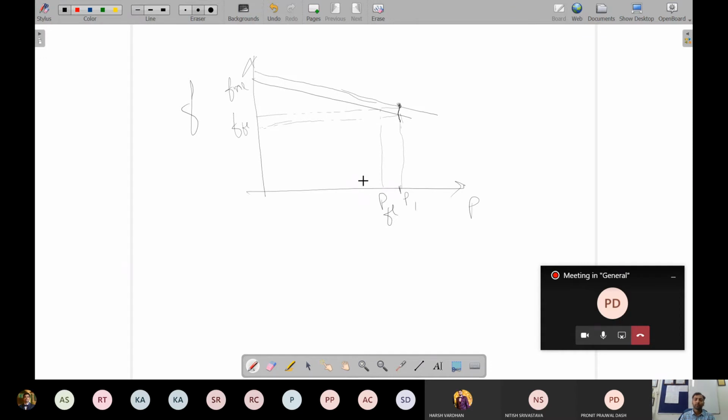And in the same way, if it shifts to this lower side, let's say P2, again we understand that if I don't do anything else, if I just keep the generator operating like that, then the frequency will tend to increase to this other value. But I don't want that to happen. So in this case I will shift the curve to the lower side, parallel to that, slightly lower, so that the intersection occurs here, and now again the frequency is constant.